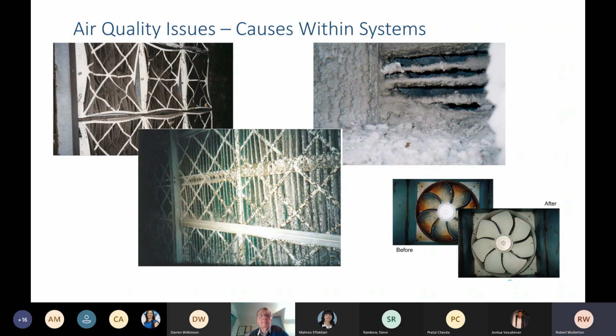So here we come on to some of the issues we find on the internals of ventilation systems. Here you can see filters imploded and also heavily clogged with debris. Site should have a regular filter changing regime, and also you can get filter bypass from the various points there. That is a regular thing that we find. Filters also heavily clogged with moisture. That's probably the most common thing we find with buildings, is not having a regular filter changing regime, and we often find that brand new filters are stacked up in the boxes in plant rooms and not actually being put into the air handling units, and you find filters like this.